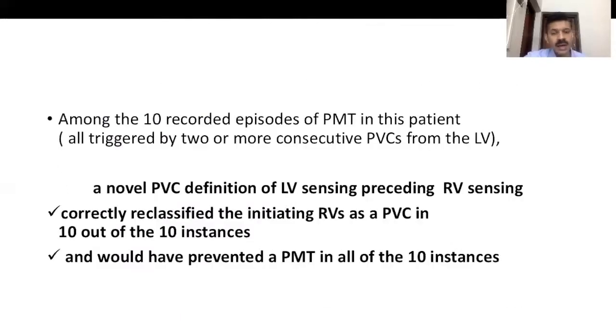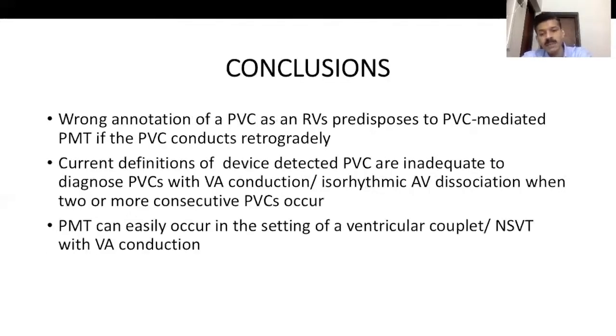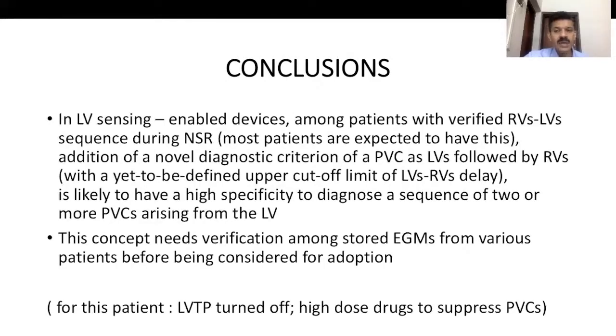So among the 10 recorded episodes of PMT in this patient, all triggered by 2 or more consecutive PVCs from the LV, a novel PVC definition of LV sensing preceding RV sensing would have correctly reclassified the initiating RV sense as a PVC in 10 out of 10 instances and would have prevented a PMT in all 10 instances. So to conclude, wrong annotation of a PVC as an RV sense predisposes to PVC-mediated PMT if the PVC conducts retrogradely, and this can happen commonly in the presence of a couplet or an NSVT. The current algorithms are inadequate to diagnose this.